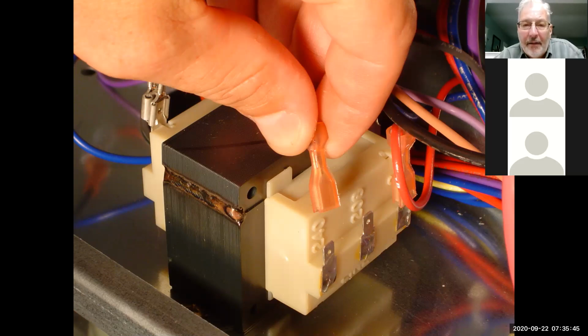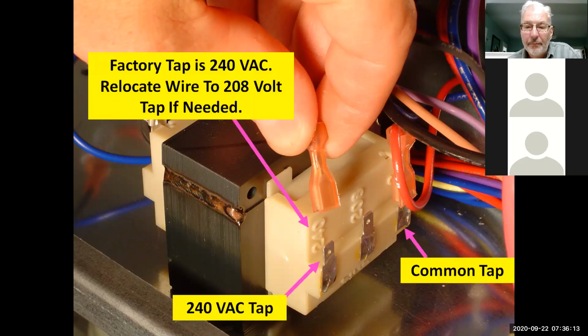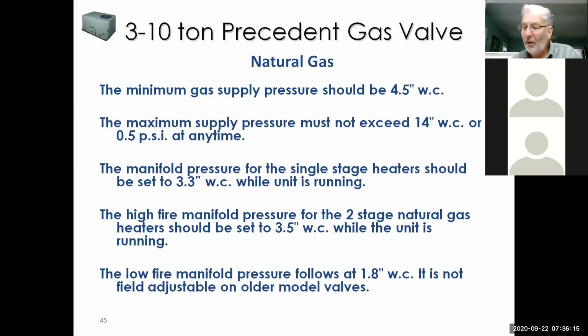Now, on that 350 VA transformer for the ignition, all that does is power the inducer and the igniter, and that transformer is not powered unless there's a call for heat. So when you're looking at that transformer to see if it's working properly, there has to be a call for heat in order for that transformer to work. That's tied into the heating circuit. Okay, so that's kind of some basics.